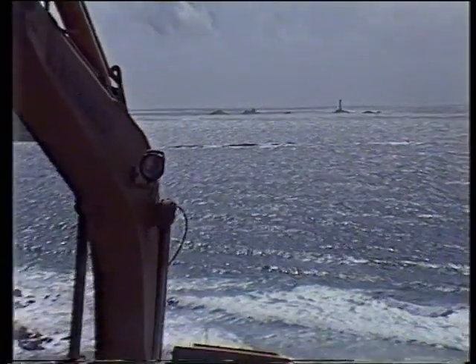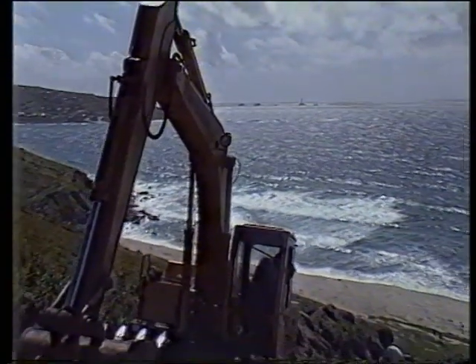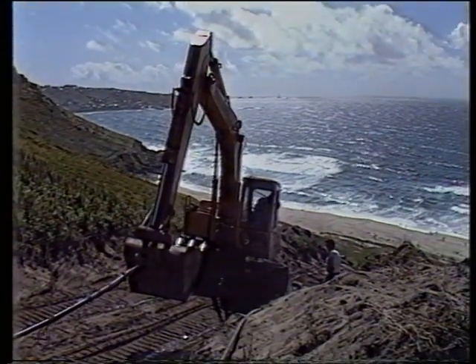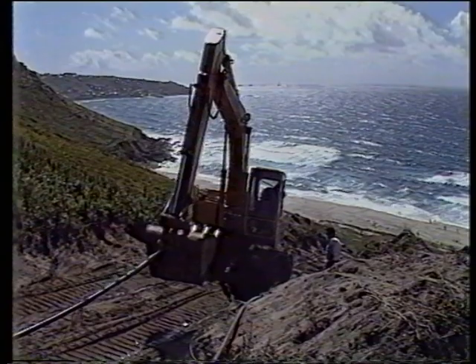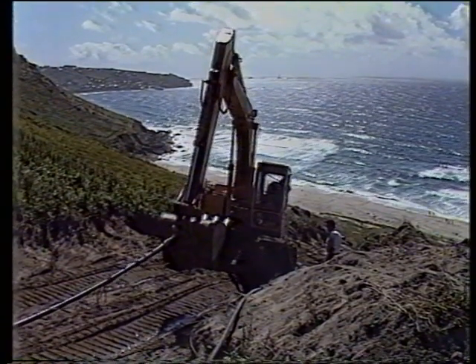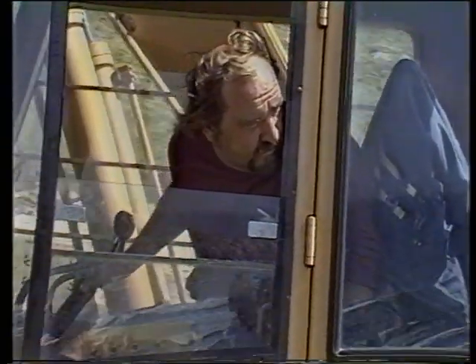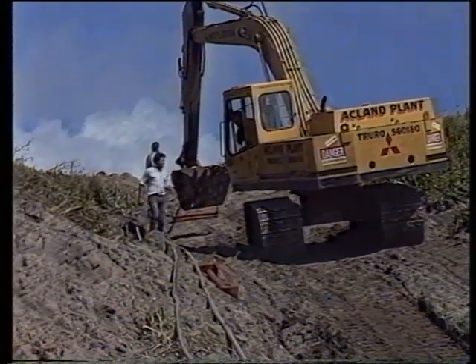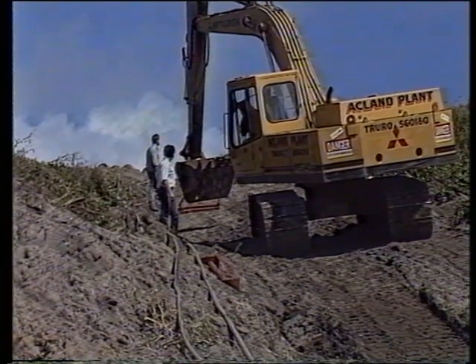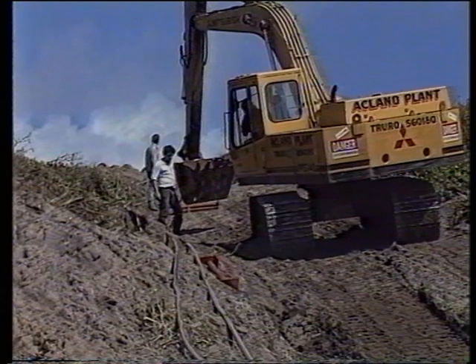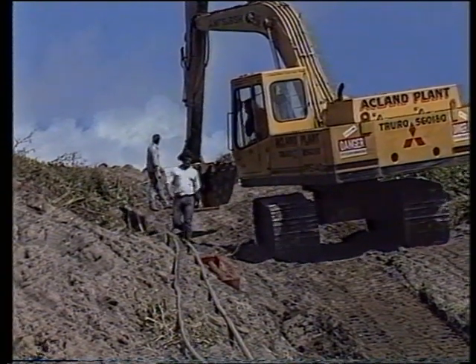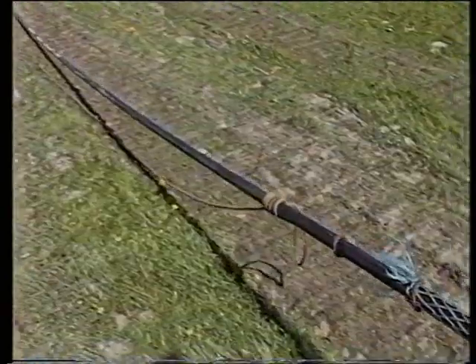On the other side of the water, near Sennon, another difficult operation is in progress. 3 700-metre-long single-core cables are being run down from the top of the steep cliff to link up with the submarine cable on the foreshore. These are made to the same design as the submarine cable cores, but separating them into 3 makes them easier to handle over this difficult terrain.